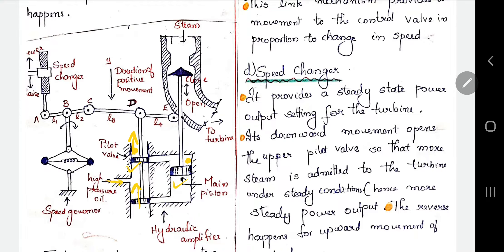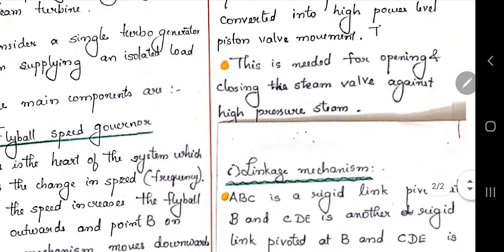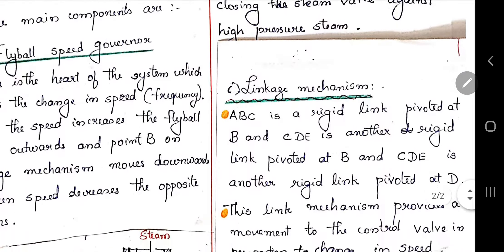The high-pressure oil goes through this part and makes the main piston move downward, opening the steam valve. If the pilot valve moves upward, the high-pressure oil enters from the other side and makes the main piston move upwards, thereby closing the steam valve. This is how the pilot valve and main piston valve work in the hydraulic amplifier — it is mainly used for opening and closing the steam valve against the high-pressure steam.